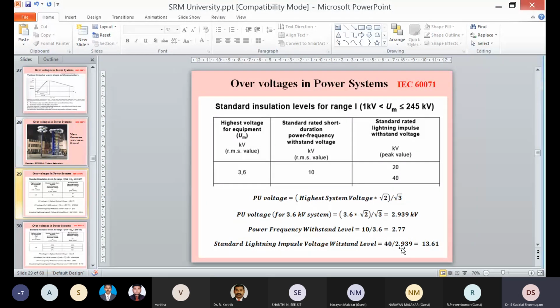So 40 kV divided by the per unit value, that is 2.939 kV, is equal to 13.61 times higher value we are considering. So your lightning impulse voltage is 13.61 times that of the per unit system value. So 13.61 per unit is the standard impulse voltage for a 3.6 kV system, whereas your power frequency voltage is only 2.77 times higher.